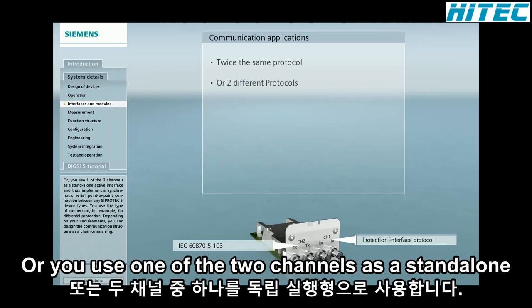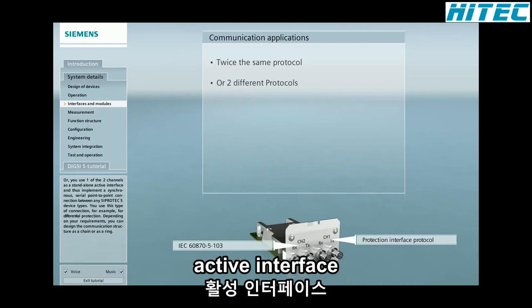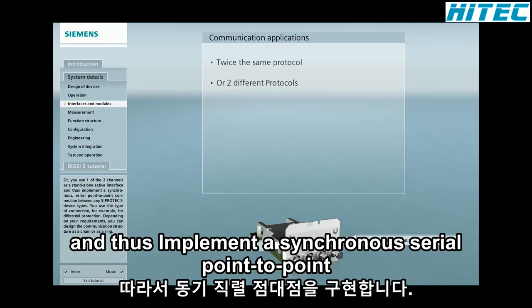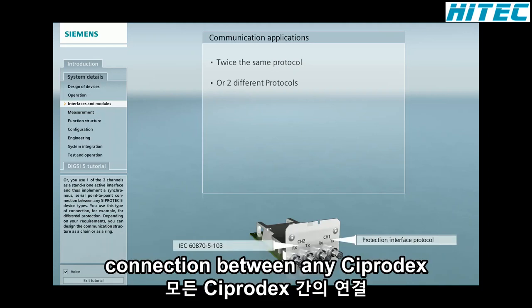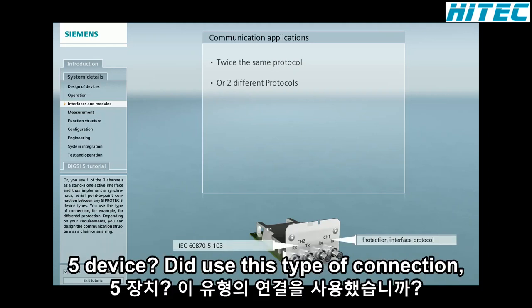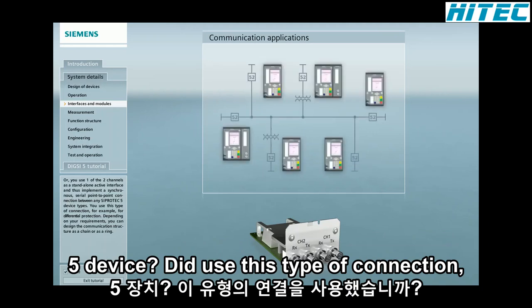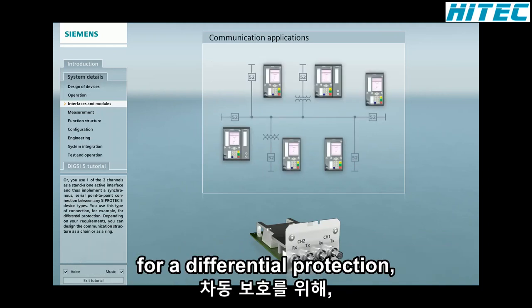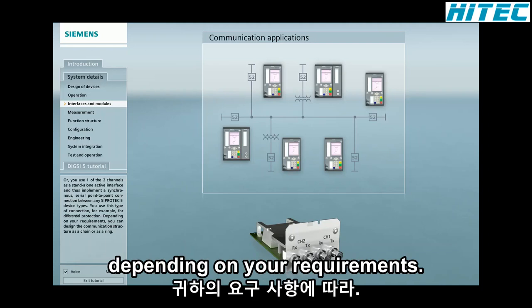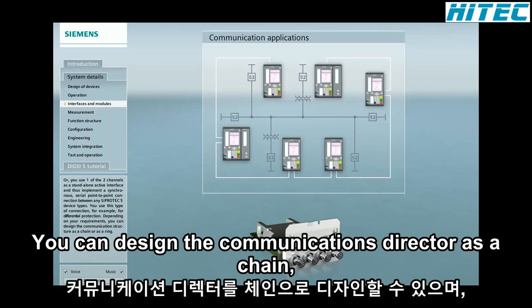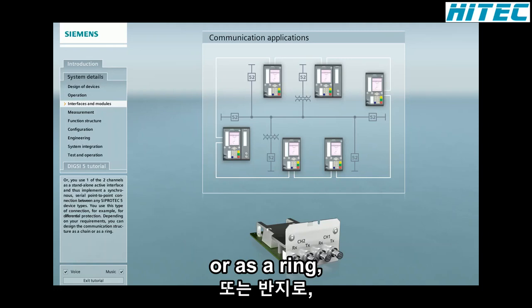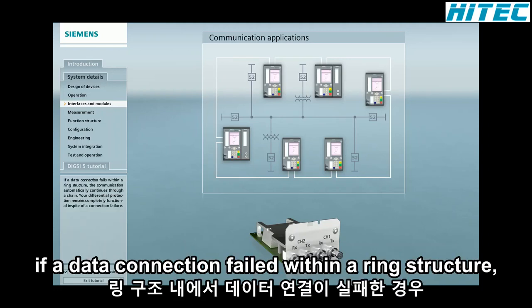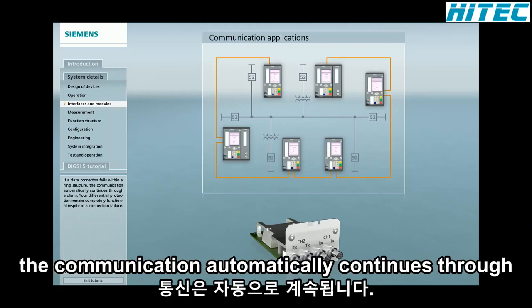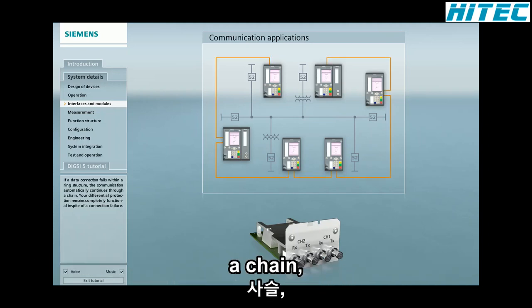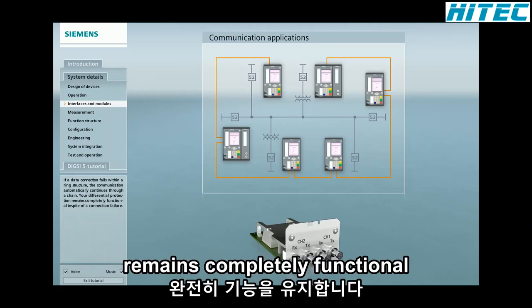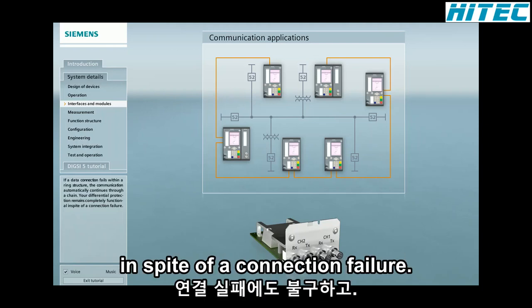Or you use one of the 2 channels as a standalone active interface and thus implement a synchronous serial point-to-point connection between any SIPROTEC 5 device types. You use this type of connection, for example, for differential protection. Depending on your requirements, you can design the communication structure as a chain or as a ring. If a data connection fails within a ring structure, the communication automatically continues through a chain. Your differential protection remains completely functional in spite of a connection failure.